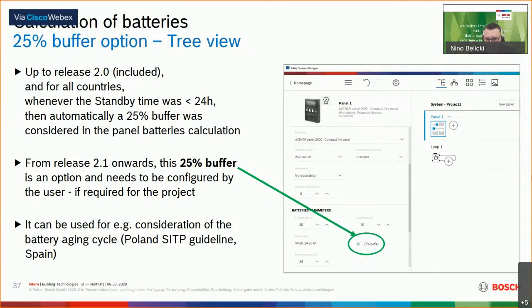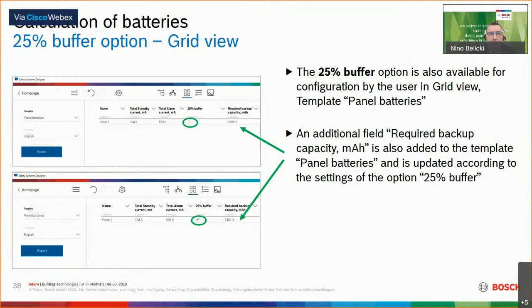This mark is a buffer which was adding several pairs of batteries always to the design, according to the VDS regulation. If you remove it, finally you can have fewer power supplies in your system. It's additional to the changes that we had last year.